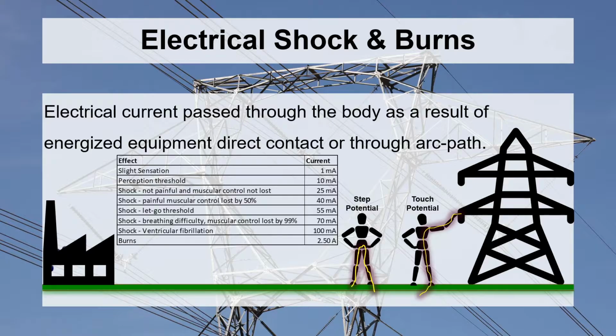That's current passing from one electrode to the other, damaging your tissue or just producing pain. Or it could be a down conductor causing a piece of steel to be energized, and you go up and touch it. The current would then pass through your body to the ground and back to the energy source. That's referred to as touch potential, where the energy path goes through your arm and down through your leg into the ground or wherever it's coming out. Or it could be just a step potential.